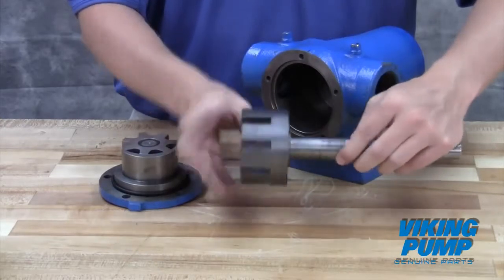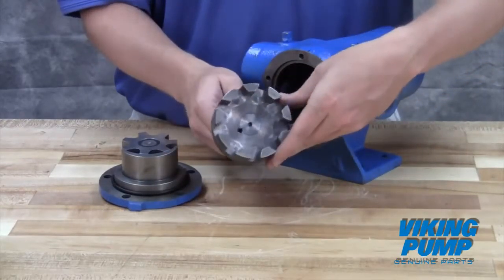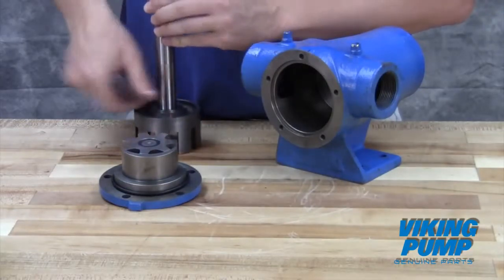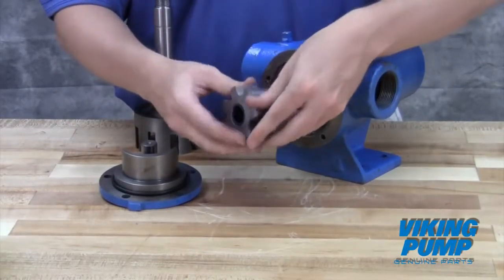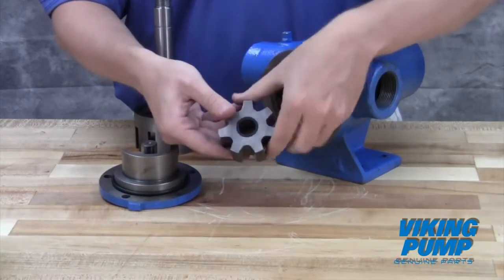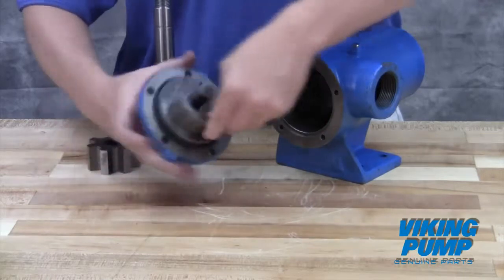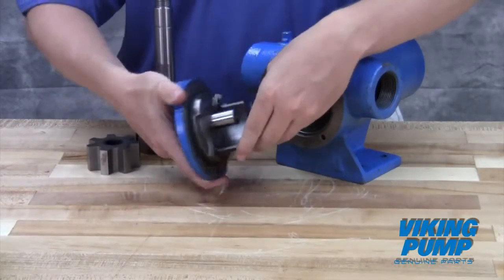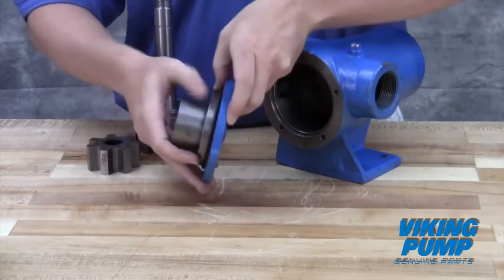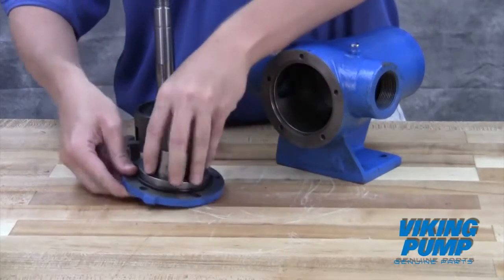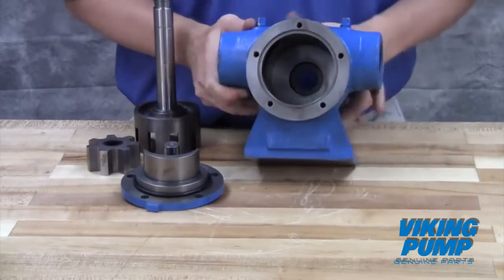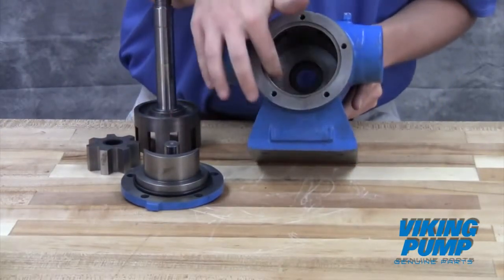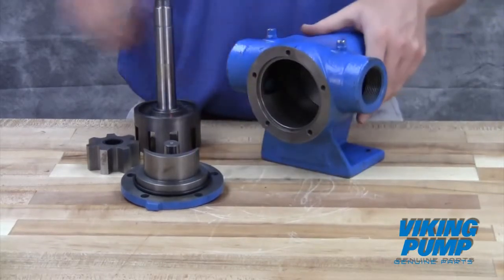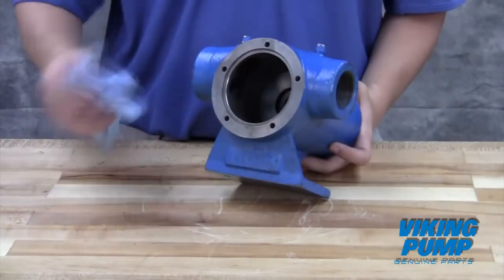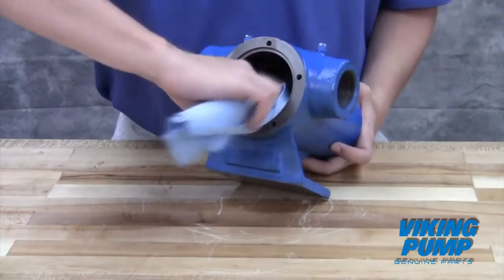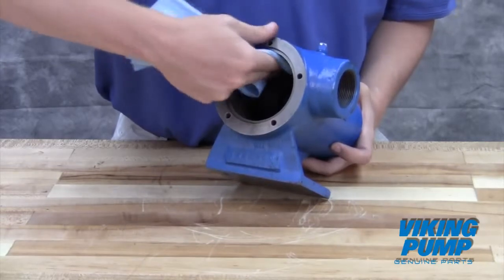Inspect the pump parts for wear, especially critical parts such as the idler pin, bushing, gears, and casing. Replace any worn components. It's recommended not to reuse seals, O-rings, or bearings unless you've been instructed to do so by Viking Pump or your authorized Viking Pump distributor. Clean the rotor hub and casing bore. Make sure both are free of dirt or grit.